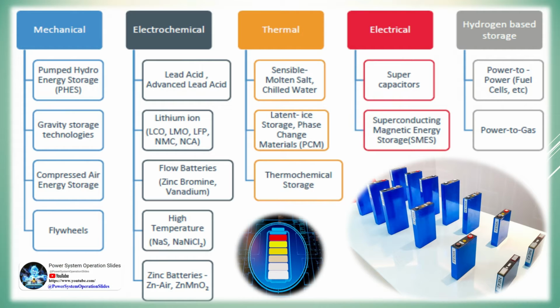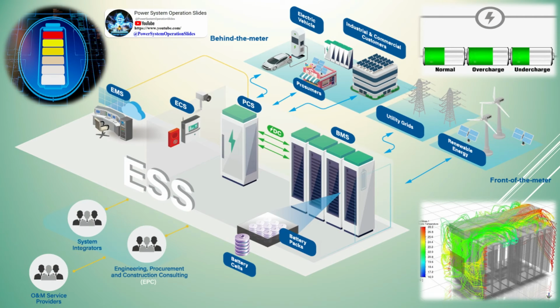In addition to the batteries, BESS requires additional components that allow the system to be connected to an electrical network. A bidirectional inverter or power conversion system (PCS) is the main device that converts power between the DC battery terminals and the AC line voltage, allowing power to flow both ways to charge and discharge the battery. The other primary element of a BESS is an energy management system (EMS) to coordinate the control and operation of all components in the system.